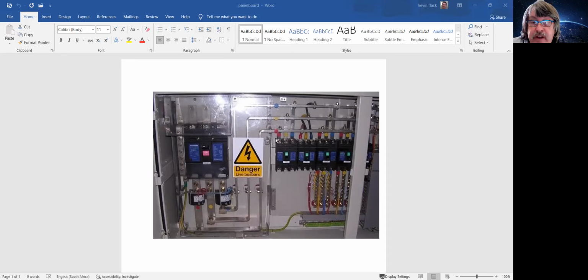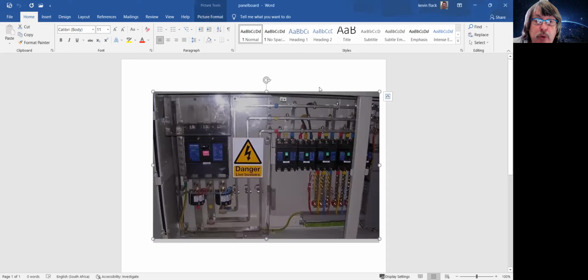We can also see that we go red, white, blue, red, white, blue, red, yellow, blue, red, white, blue, red, white, blue. And breakers that are put together, completely together, where there's no gapping in between, will require a barrier fitted in that zone as well. Or the alternative to this would be maybe red, white, blue, red, white, blue, blue, white, red going through here. So we could have a look at that as an option to having the interface barriers.